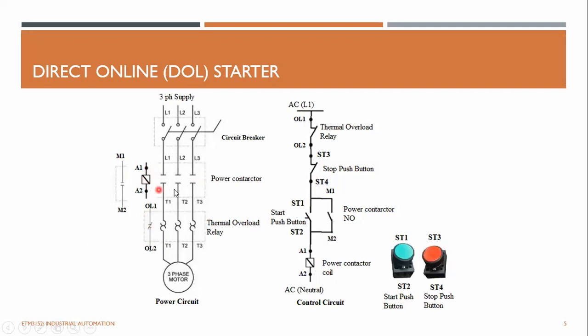So for this main contactor, this is a contact coil, and it also has an auxiliary contact, M1 and M2. Right, so this is the control wiring. We can use start and stop push buttons, so momentary push buttons. Once you press it and release it, and push this one, stop, you press and release, it will do the job. You can see here now the thermal overload.